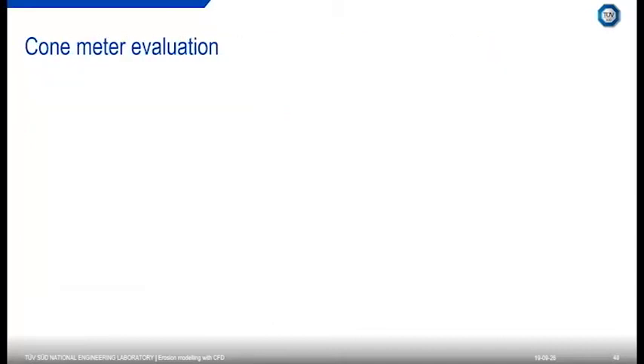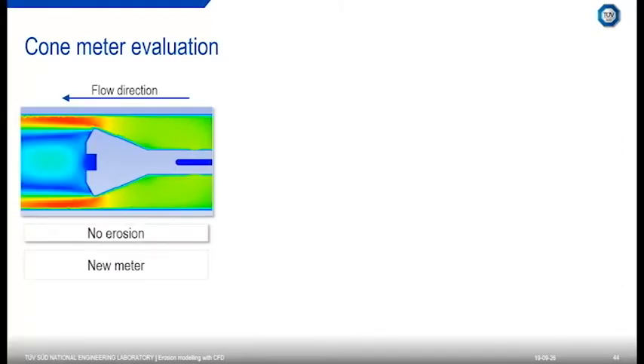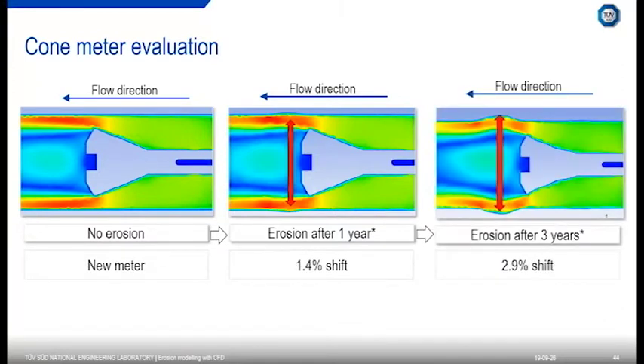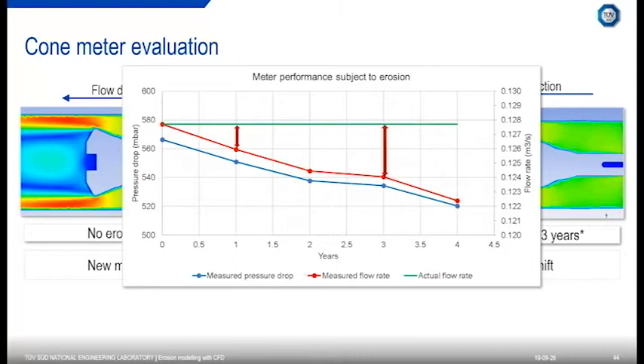Here we have a plot of velocity — the flow is accelerated at the restriction after the cone. This is our new metre with no erosion yet. After one year at a particular flow rate, downstream of the cone metre the actual pipe is becoming larger, resulting in a different downstream pressure, so our differential pressure is changing. After three years it's even larger and we have an even larger shift. We plot the actual flow rate in green as constant, and the measured flow rate based on the measured pressure drop changes over time — this shows how much of a shift is impacting the measurement, and when we might need to recalibrate the metre.